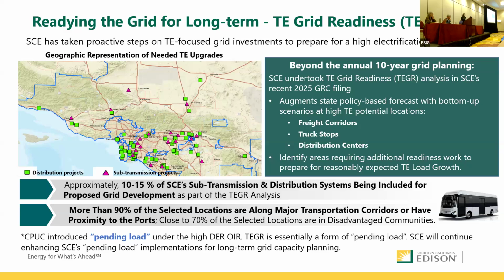In California, the three investor-owned utility companies are required to use a state forecast, the CEC IEPR forecast. Each utility then takes that forecast and disaggregates it down to the circuit level for distribution planning. We've observed challenges with this top-down disaggregation approach, because with top-down you're probably getting little bits here and there, maybe 0.1 megawatt on a circuit. However, in reality we're seeing some very big projects, 5 megawatt, 10 megawatt, even 30 to 40 megawatt EV projects coming to the distribution system.